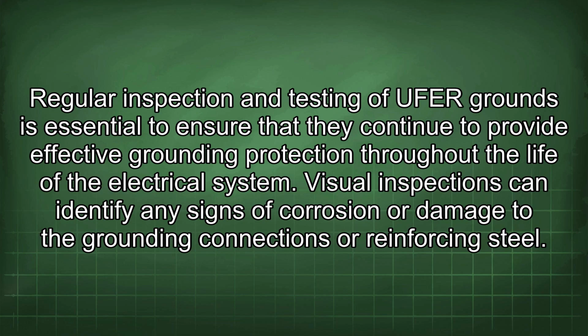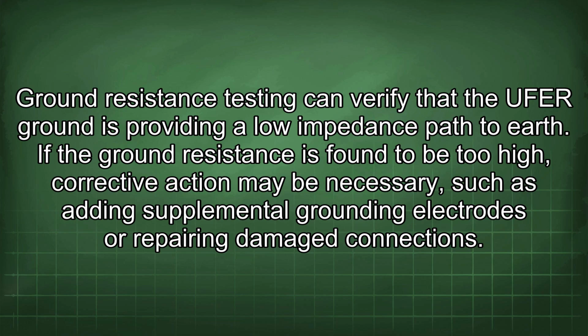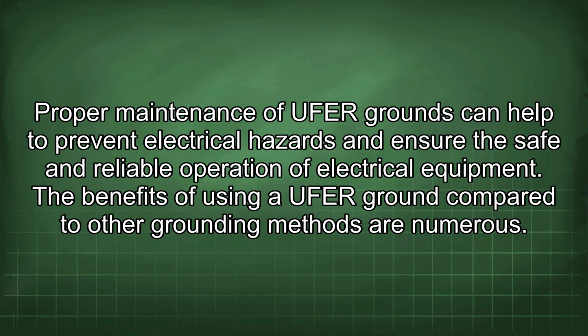Regular inspection and testing of UFER grounds is essential to ensure that they continue to provide effective grounding protection throughout the life of the electrical system. Visual inspections can identify any signs of corrosion or damage to the grounding connections or reinforcing steel. Ground resistance testing can verify that the UFER ground is providing a low impedance path to earth. If the ground resistance is found to be too high, corrective action may be necessary, such as adding supplemental grounding electrodes or repairing damaged connections. Proper maintenance of UFER grounds can help to prevent electrical hazards and ensure the safe and reliable operation of electrical equipment.